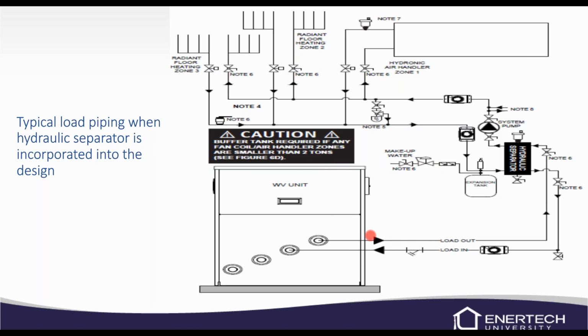So if the WV unit needs 15 GPM and you've got a small air handler that needs 3 GPM, if the air handler was calling, we had 3 GPM and we did not have the hydraulic separator, the unit's not going to get enough flow. We have a bypass valve that'll allow the extra flow to go through, but it causes the unit to short cycle and things like that. So the better setup is to install a hydraulic separator, and then the unit will flow through the hydraulic separator and go back through and get its 15 GPM. Now the zone will pull through the hydraulic separator and just pull the flow that it needs to the air handler. So we decouple the two right here at this hydraulic separator.